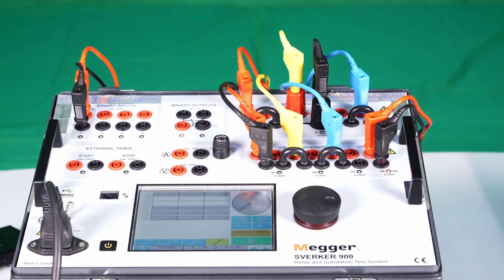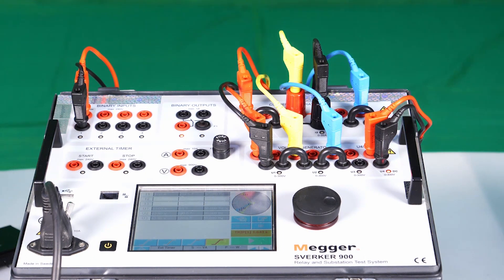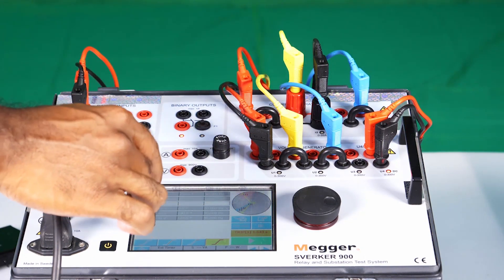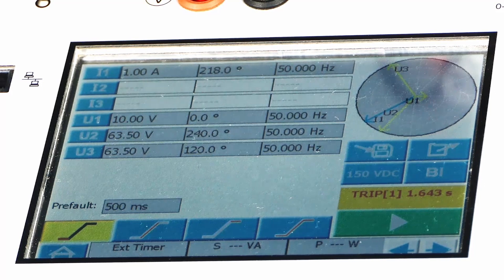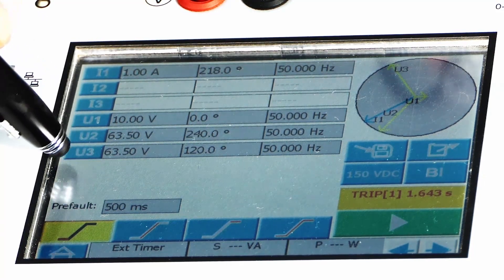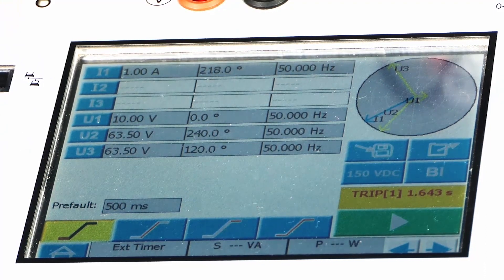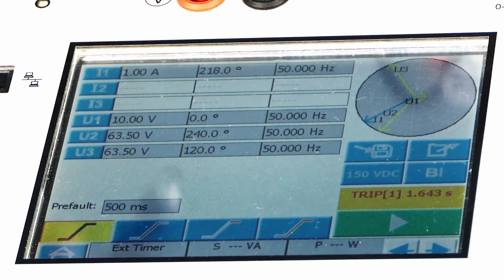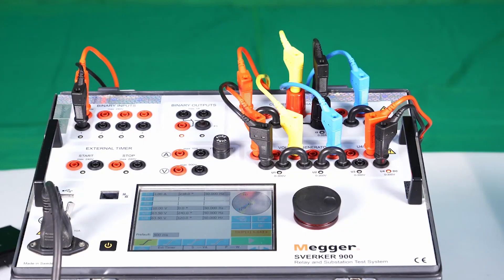Let's verify the boundaries at 30 degrees and 220 degrees separately. In the Ramping Screen, the magnitude of R-Phase current is configured for 1 Amp, which is greater than the settings. The R-Phase voltage is dipped down to create a real-time fault situation, while Y and B phases have healthy voltages. The voltage of the respective phase is also configured for suppressed voltage to simulate the neutral unbalanced condition.